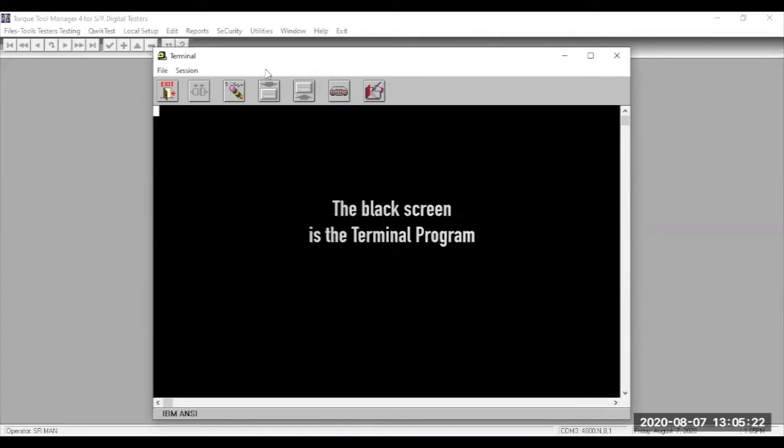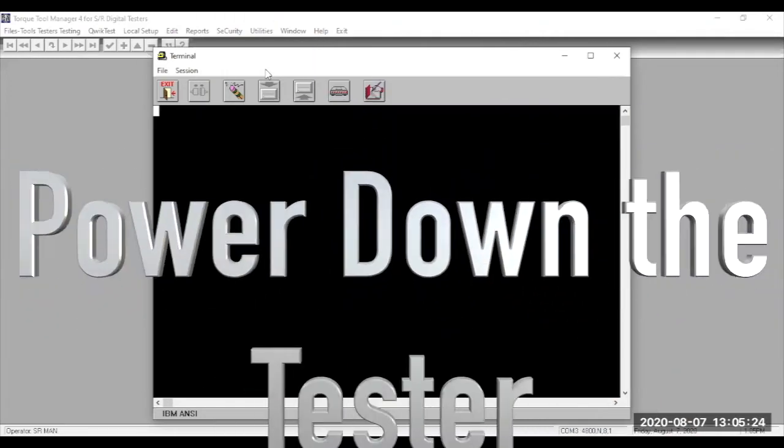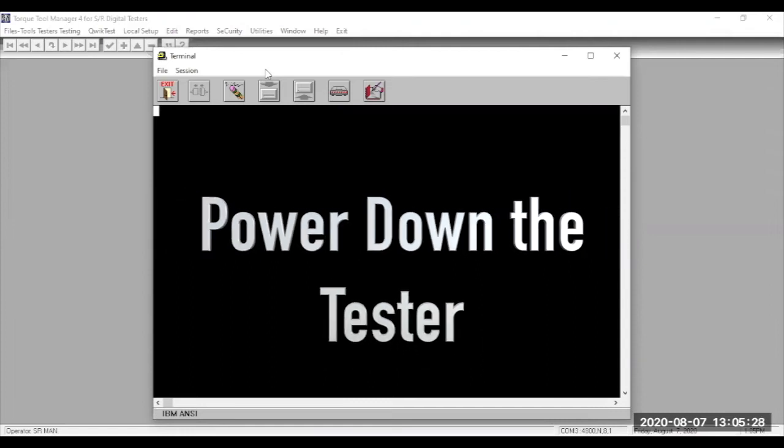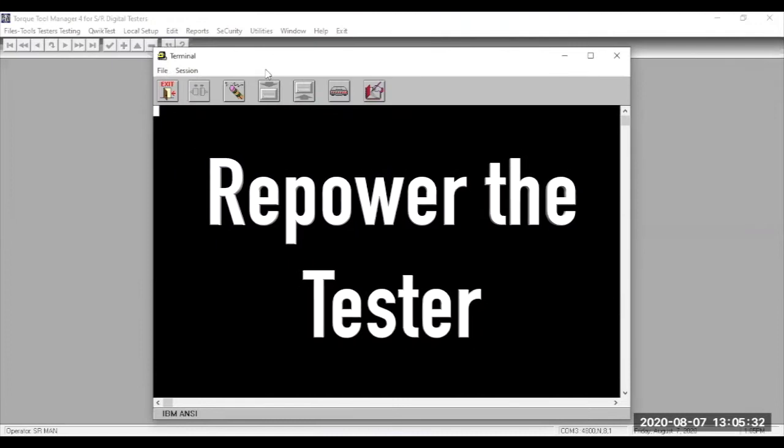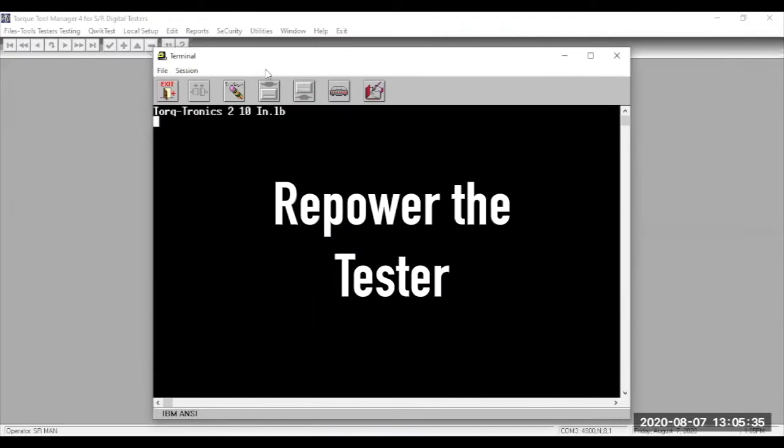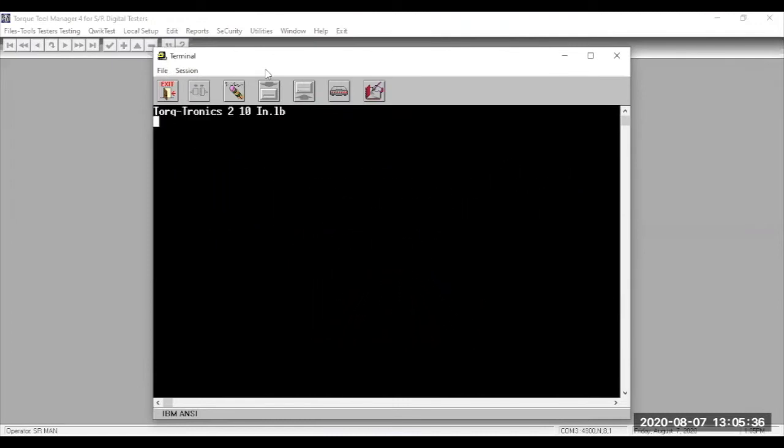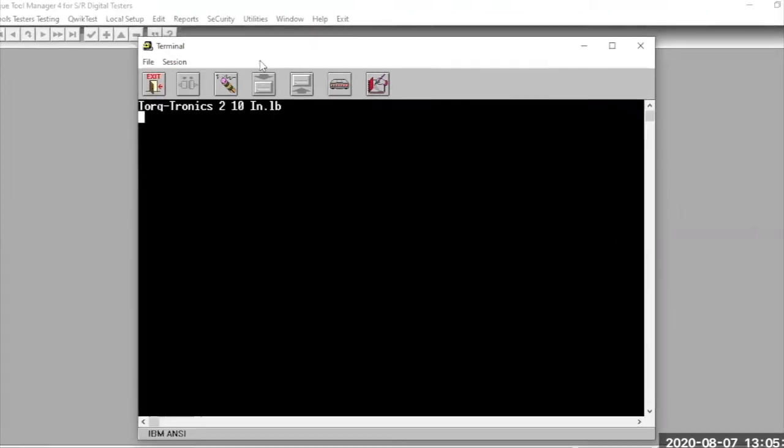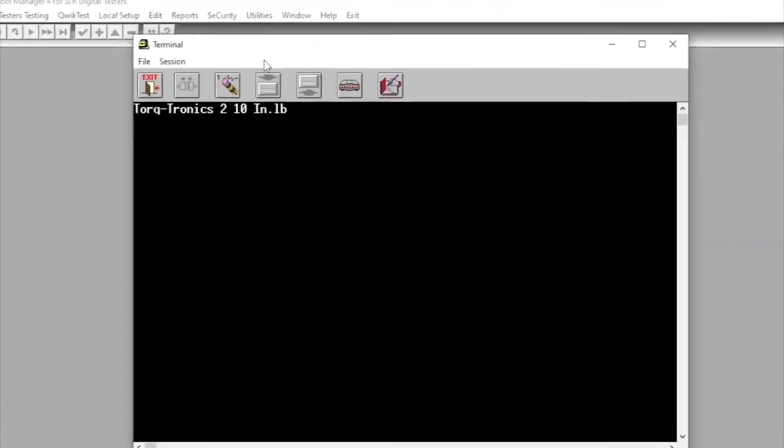Next, shut off the power to the tester and count to 7. After you reach 7, flip the power switch back on so the tester now has power. You should see the name of the tester and its capacity appear in the top line of the terminal window.